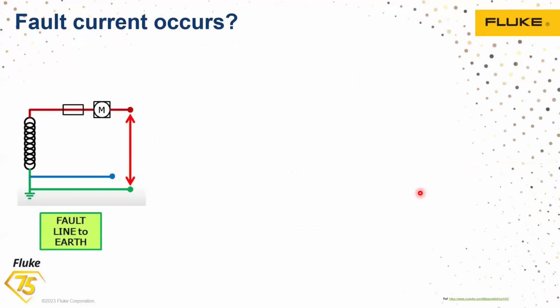So let us understand where the fault current occurs from. Earth fault loop impedance is closely related to the protection of the electrical system. The primary purpose of determining the earth fault loop impedance is to ensure that the protective devices in an electrical installation, which may be a circuit breaker or a fuse box, are able to quickly detect and interrupt the flow of fault current. Whenever such an event occurs, the earth fault current flows between the phase and the earthing.